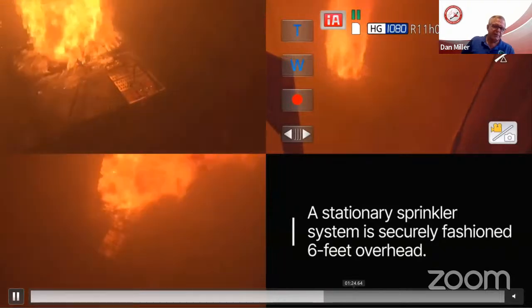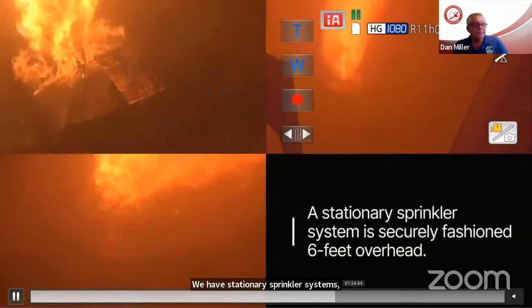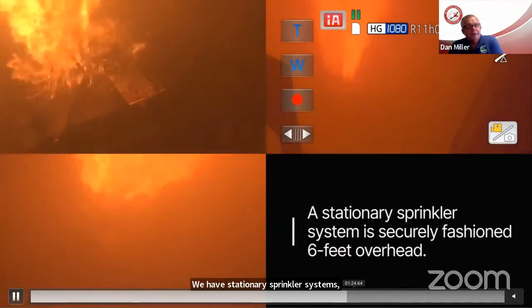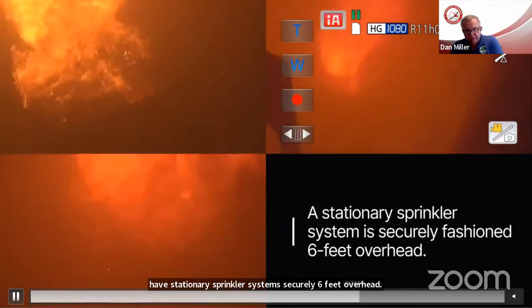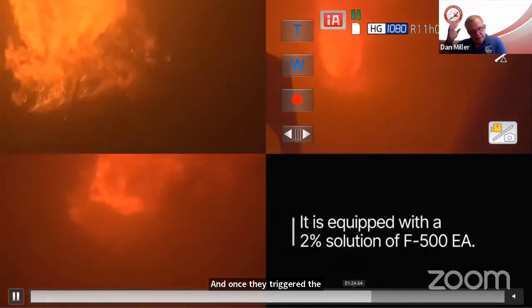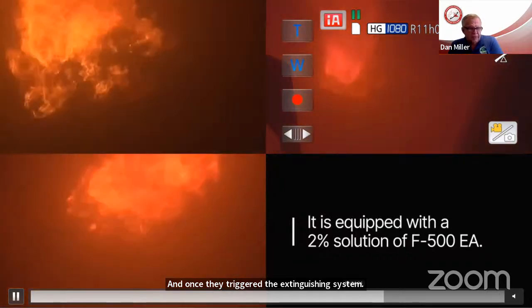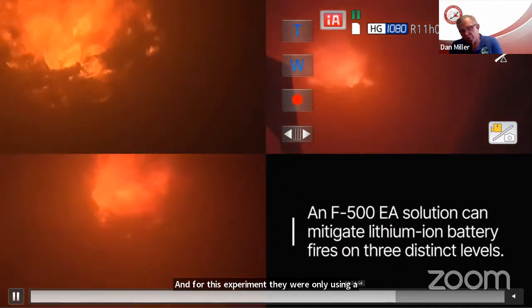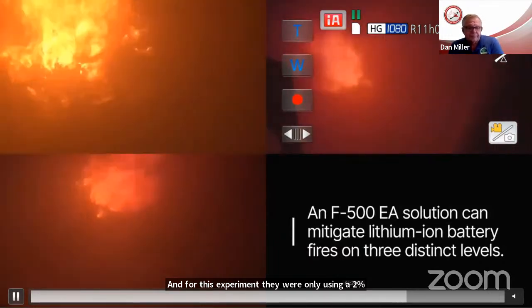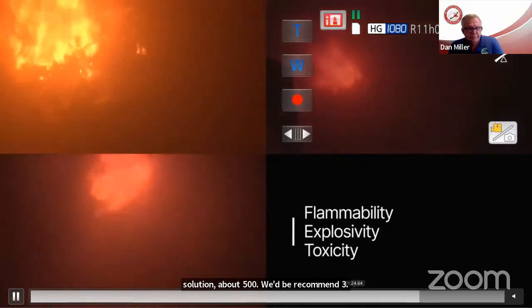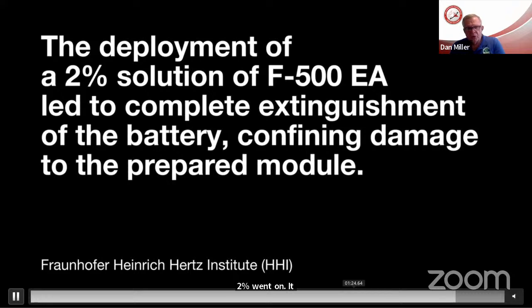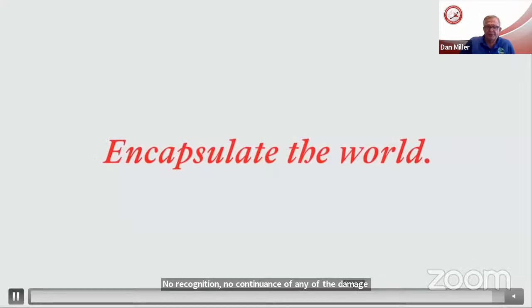We have stationary sprinkler systems securely fashioned 6 feet overhead. Once they triggered the extinguishing system, the battery goes quickly out. For this experiment they only used a 2% solution of F500, though we recommend 3%. That 2% went on, darkened it immediately, and there was no reignition or continuance of any damage to the batteries. It was immediately stopped.